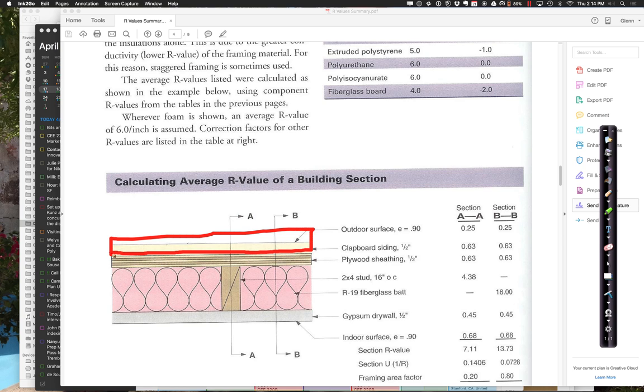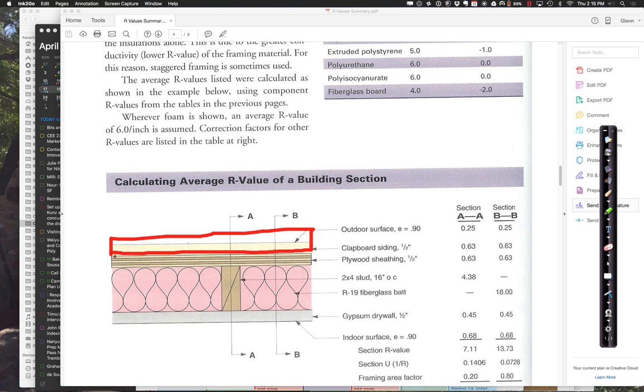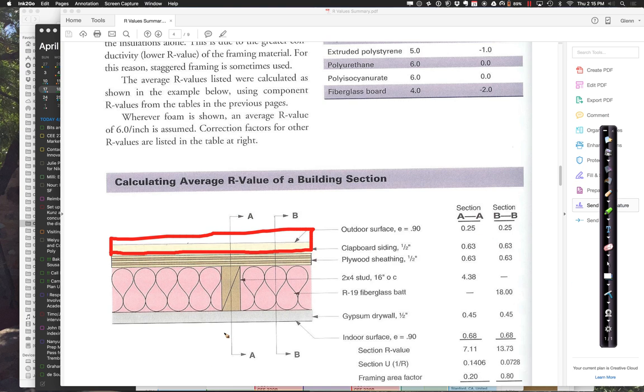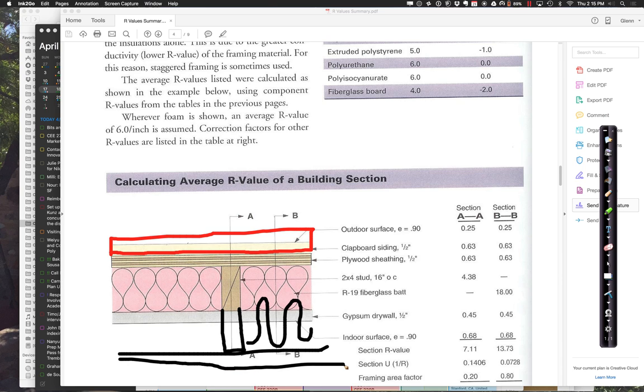So far so good. We still have a weak spot there. Even though I've increased it by 12, that is still a weak path. The 2x4 stud has a value of around 4.38, whereas the batt insulation had an R value of like 18. So let's talk about is there any way you can think of to eliminate that problem where I have a weak link going through?